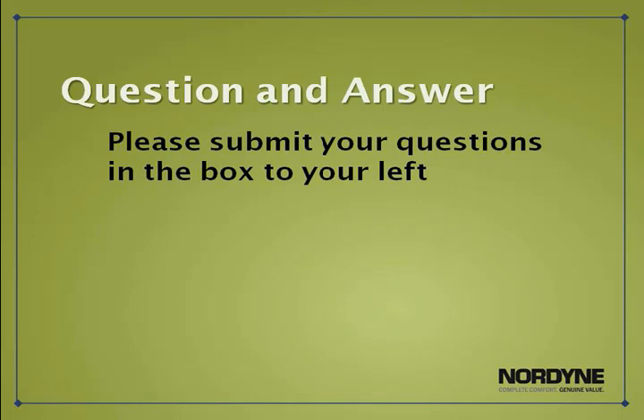Jay with RE Michael is asking if there's a dedicated charge mode, and no, there's not. Essentially, when you input at the start of the cycle a Y1, Y2 input, the unit will always start at C4, run there for 45 minutes. You need to do your charging within that 45-minute period of time. If you need to still continue to charge the unit after that 45-minute period of time, you need to cycle down the unit, restart it back up in that C4, and continue adding charge from there.